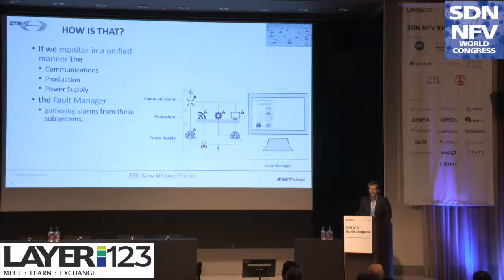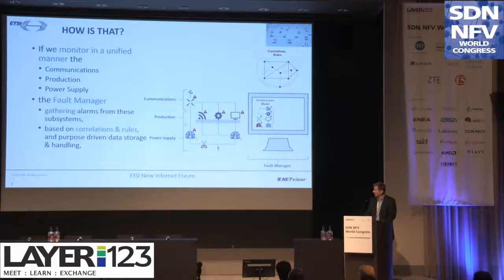Infrastructure monitoring and supervision, how is that? Let's see in detail. If we monitor these subsystems in a unified manner, the communications or ICT subsystem, the production subsystem, and the facility, which means basically the power supply, then the fault manager builds an infrastructure and fault model and gathers alarms from these subsystems based on correlations and rules and purpose-driven data storage and handling.